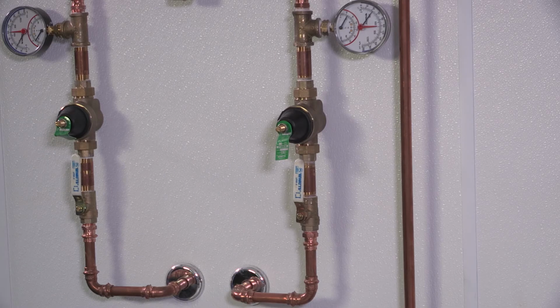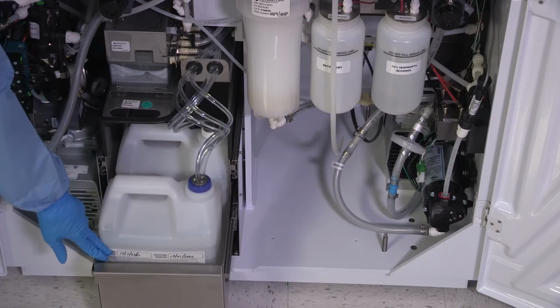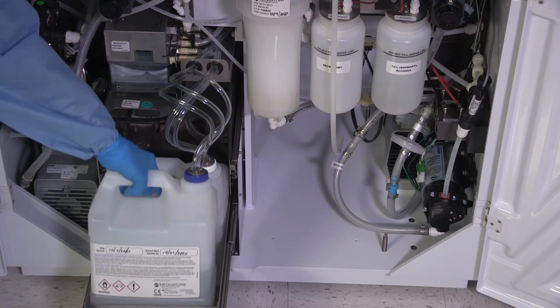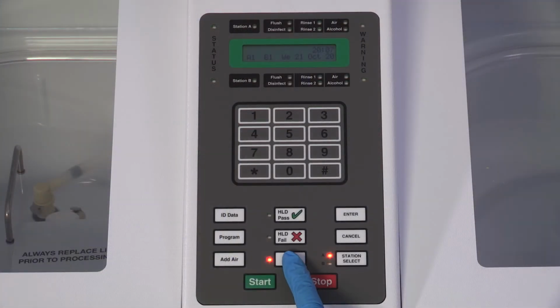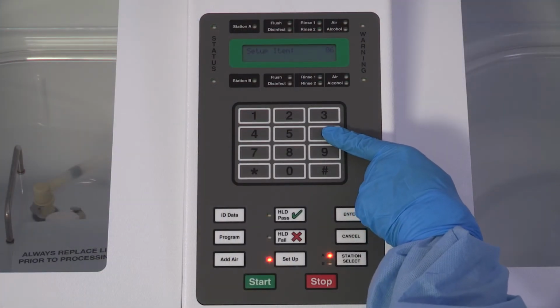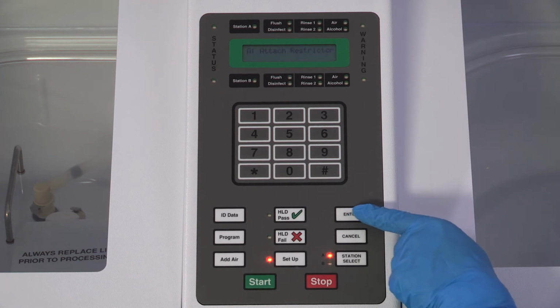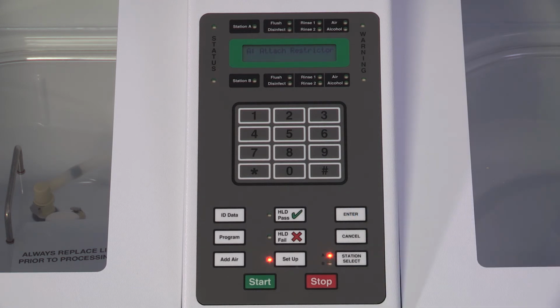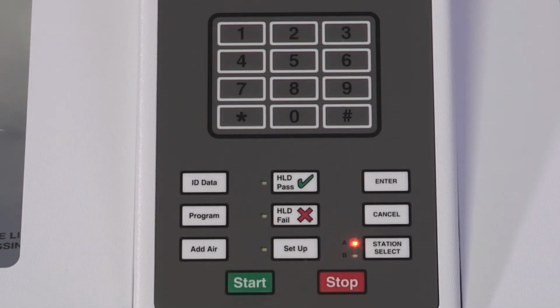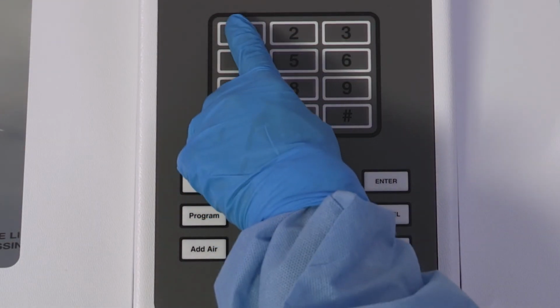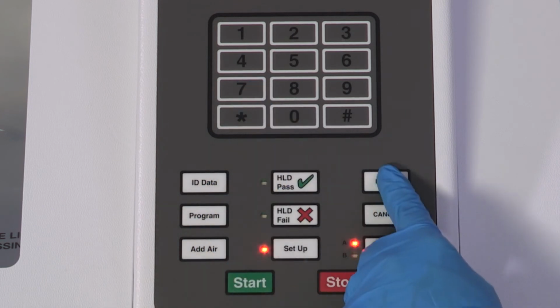Ensure the water is on, and there is approximately 1 inch of fluid in each Rapicide PA disinfectant container. Press Setup, 6, Enter. The display will prompt Attach Restrictors, which should be installed in both basins. Press Start. The waterline disinfection begins. The rest of the process is automatic and takes approximately 2 hours. If desired, the time remaining can be checked by pressing Setup, 17, Enter.